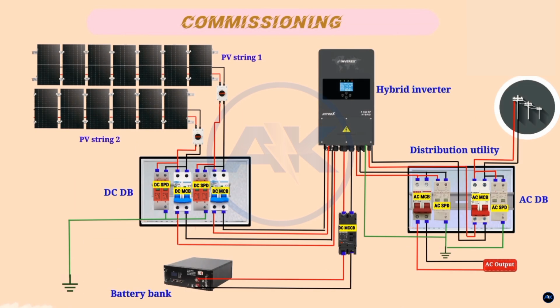And we are now on the commissioning. The very first thing on our list is to turn on the MCCB for the battery bank. The second thing to do is turn on the power switch, which is located at the bottom. From this moment on, you have to give your inverter a few seconds before doing anything else, and you have to be very attentive and read the display of your hybrid inverter.